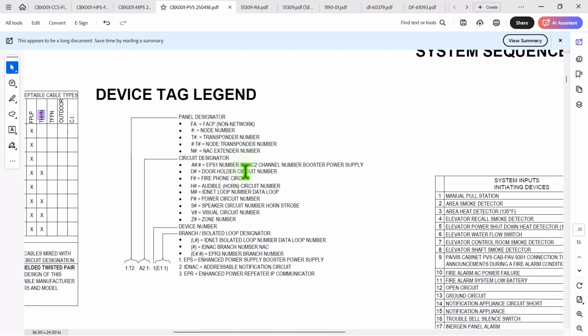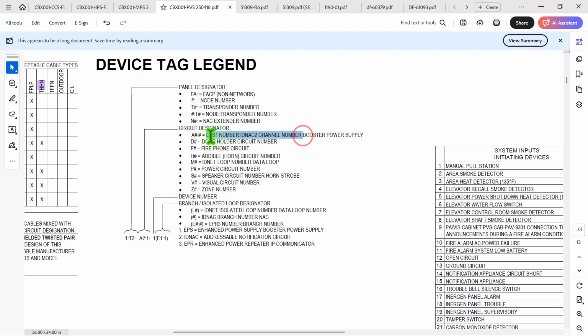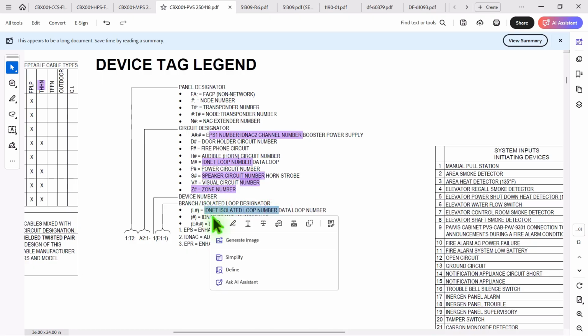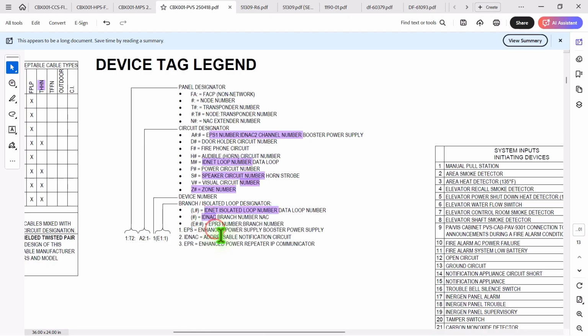Down here this stuff is good. We're just going to have booster power supply, we're just going to put data loop. This is just going to be horn strobe circuit - remove this, there's no zones for this. Remove this, this is just data. Remove IDNAC and just leave it as branch NAC circuit. Remove enhance, this is just a regular power supply.